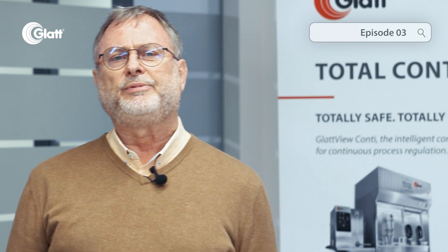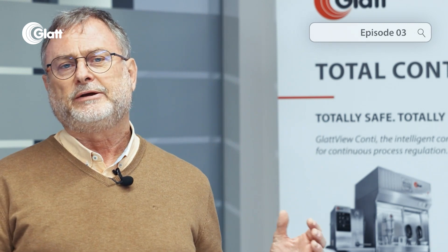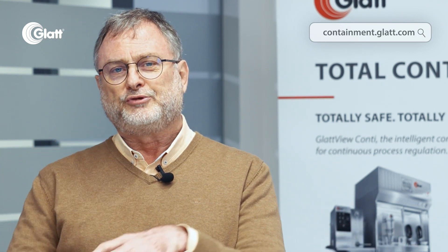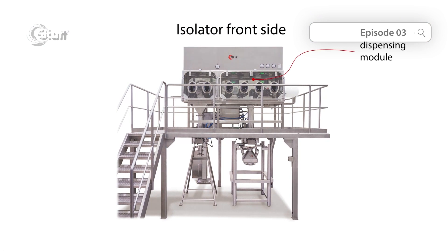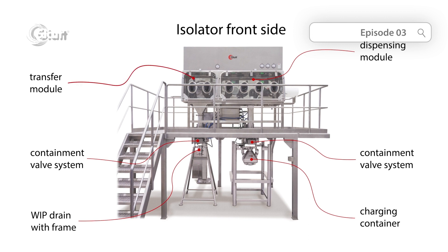Isolators are the mechanical barrier between the operator weighing an ingredient and the dust cloud that is created during this weighing process. But it is not only the mechanical barrier that protects the operator. In addition, a constant negative pressure of one millibar or 100 Pascal is maintained in the isolator.